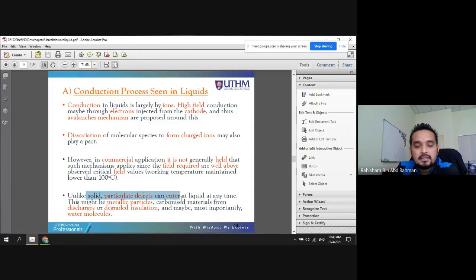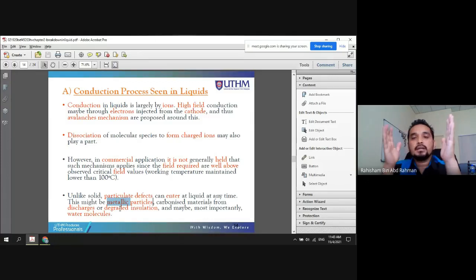Another issue is the conduction process, the particulate defect. For example, we have metallic particles from the winding, from the wall of the tank, from the top and the bottom of the tank. These metallic particles will deposit or move within the liquid, and this phenomenon will trigger discharge formation within the dielectric material, and hence it will degrade the insulation oil.